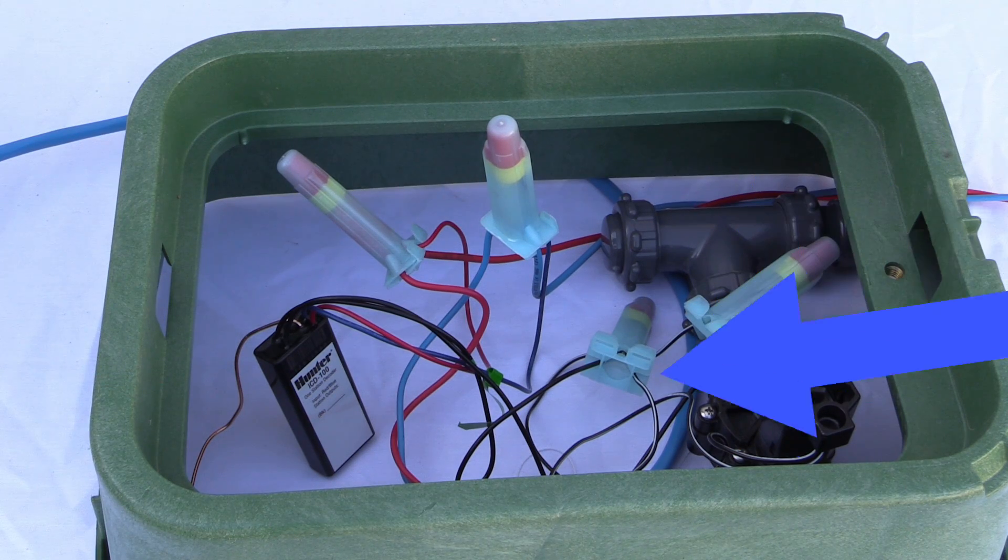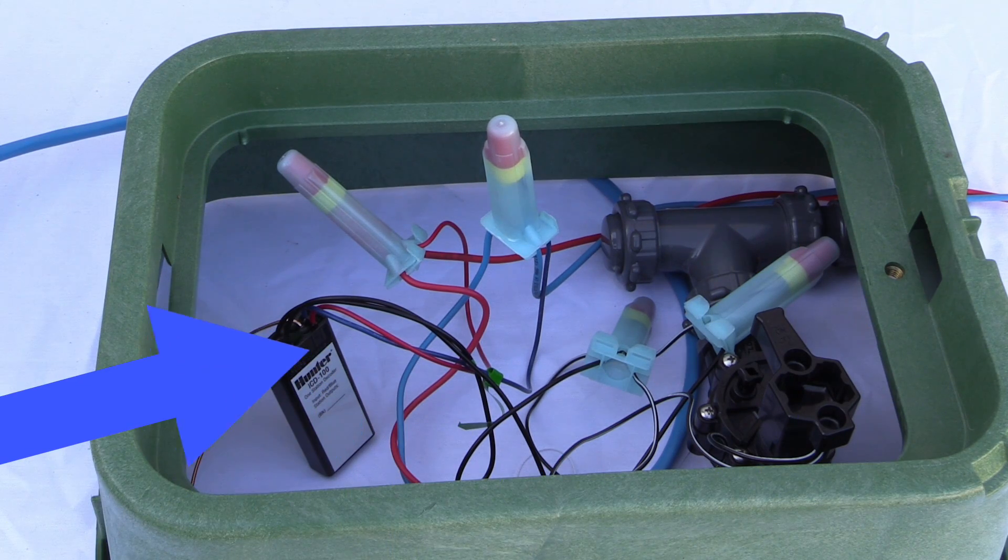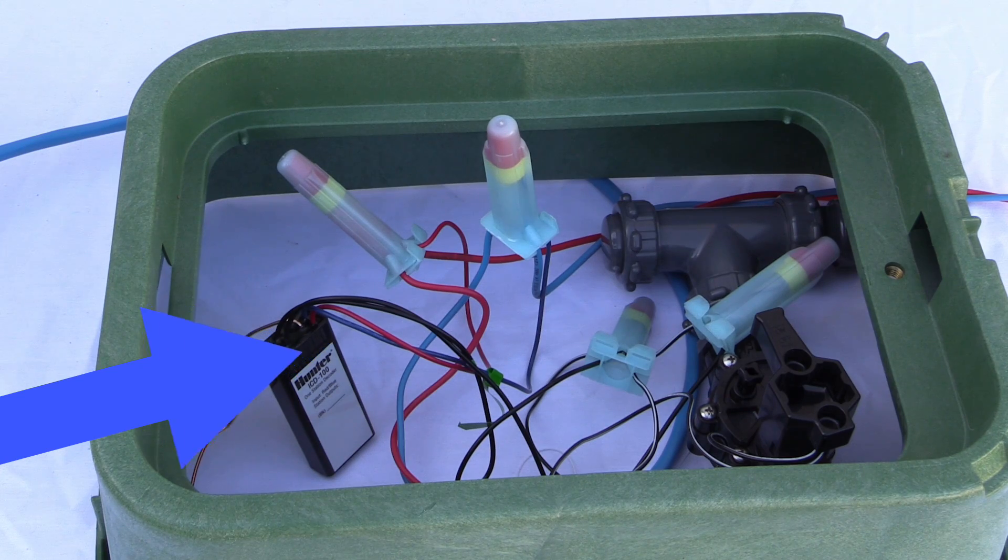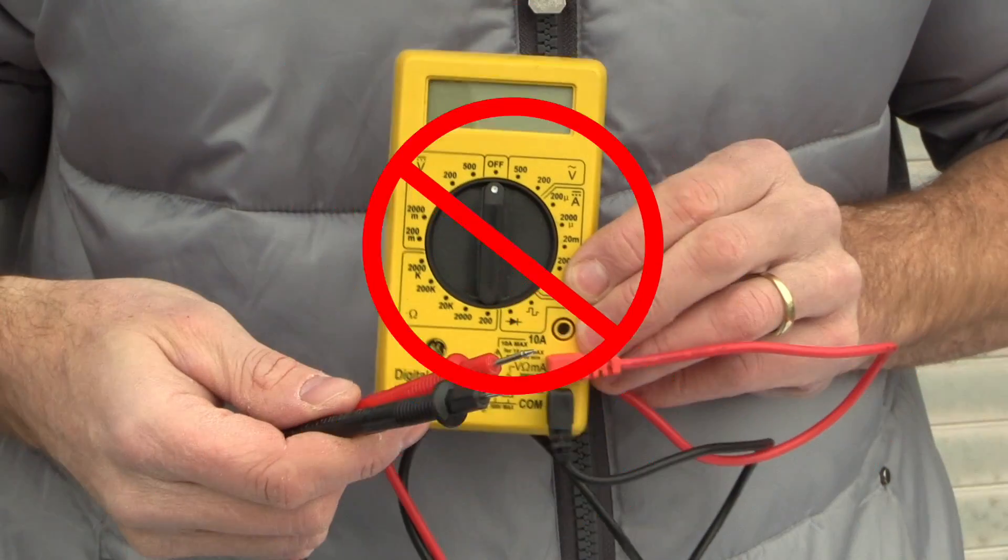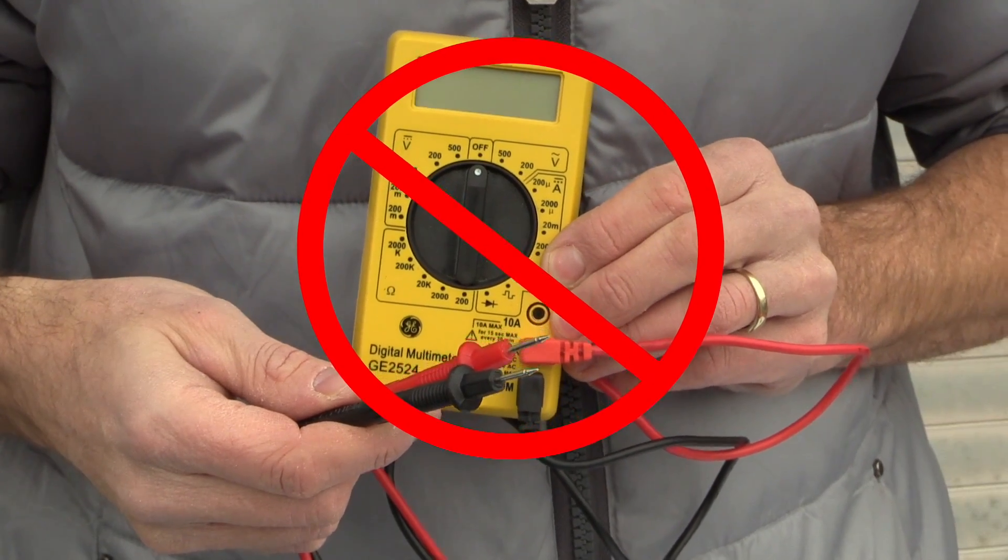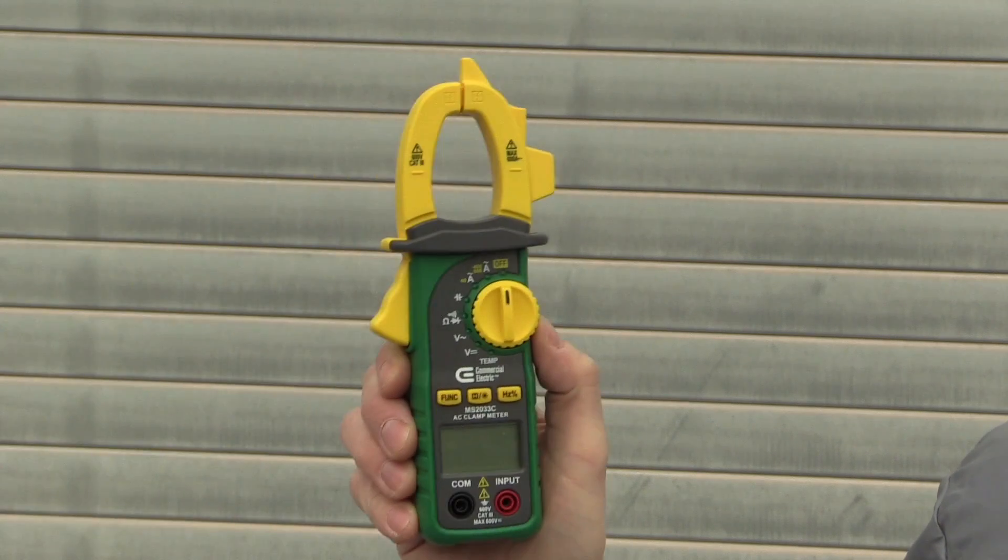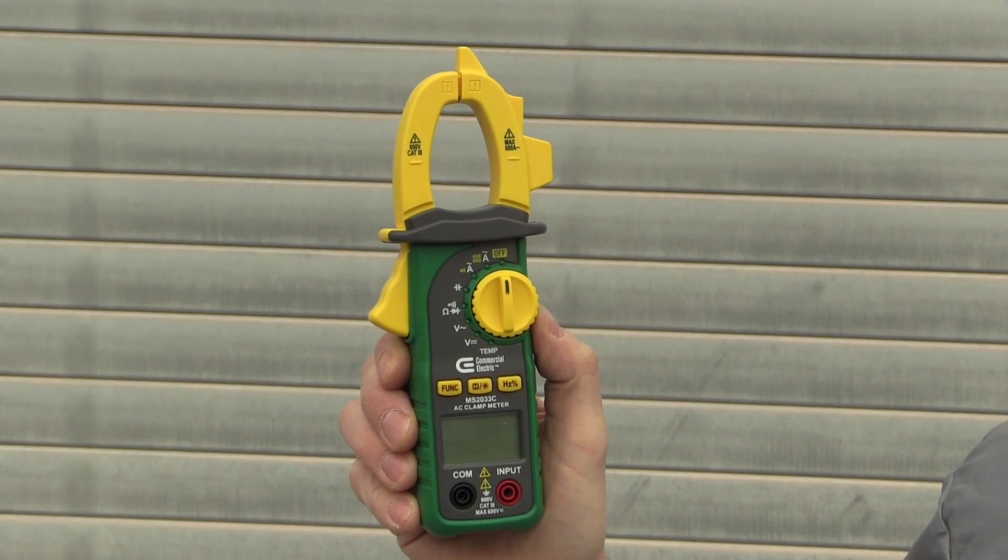Because valve solenoids are after the decoder, it's not possible to use traditional resistance measurements with an ohmmeter to measure the health of the circuits. Instead, we will demonstrate use of a clamp meter to measure current flow.